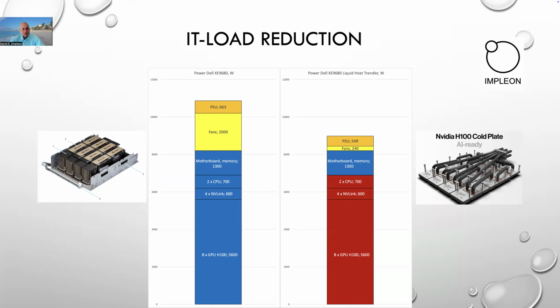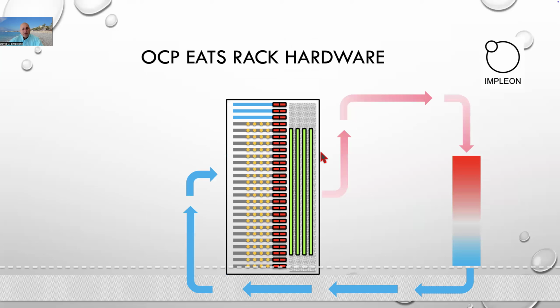Another thing is the energy consumption of the IT equipment itself. So we can compare GPU servers. On the left, you can see an air-cooled server, and you see that among the overall energy consumption, the fans' energy consumption is 2 kilowatts, and the power supply unit provides all that energy for all components. On the liquid-cooled one, we have the same amount of IT components, and this part is liquid cooled, but that allows us to reduce the energy consumption of the fans, which cover only this part of air-cooled components. And that reduction overall also allows us to reduce the power supply and energy consumption. So overall, we reduce from 11 to 9 kilowatts.